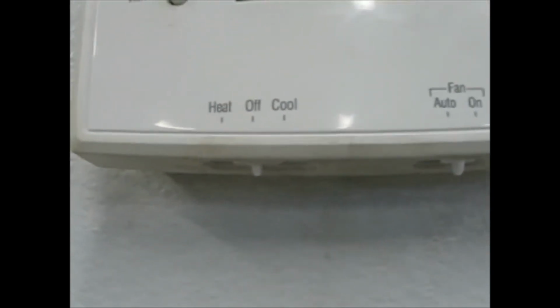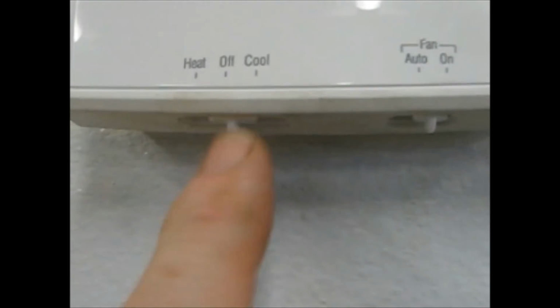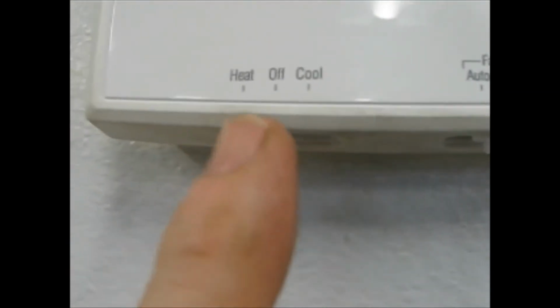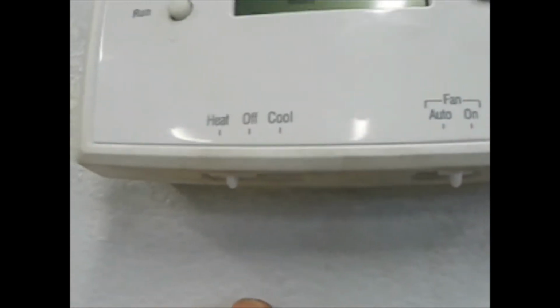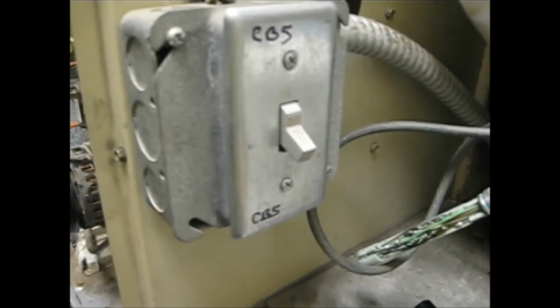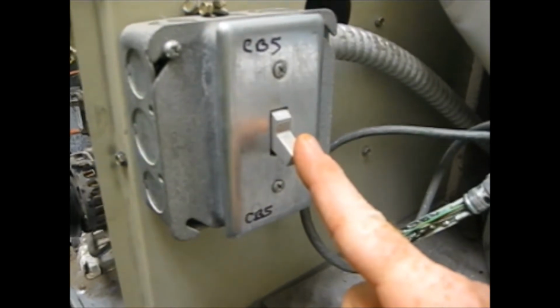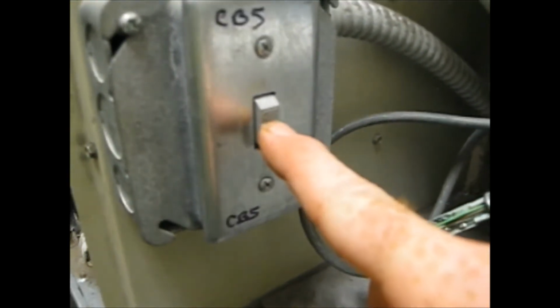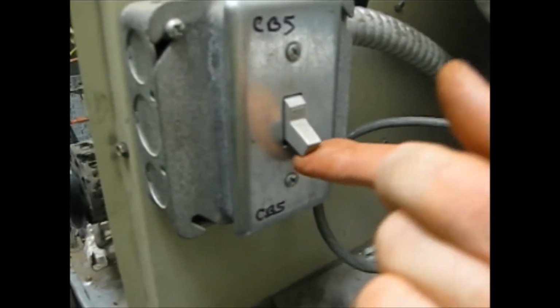Also make sure that your thermostat is not in the off position or the cool position. Make sure it's in the heat position. Each furnace should have a safety switch or cutoff switch nearby. This one right now is off, but make sure your switch is actually on.